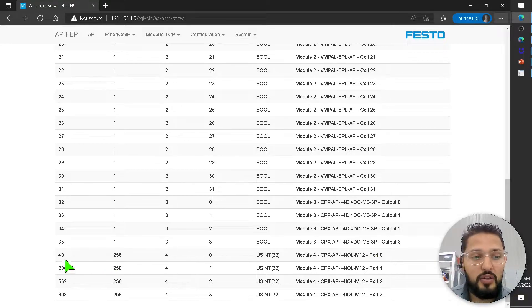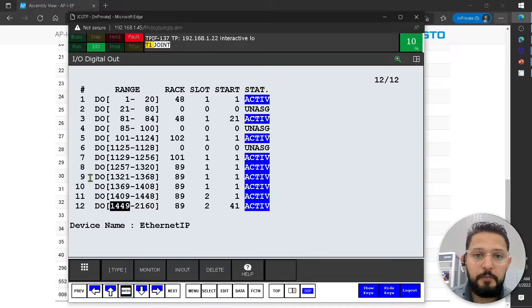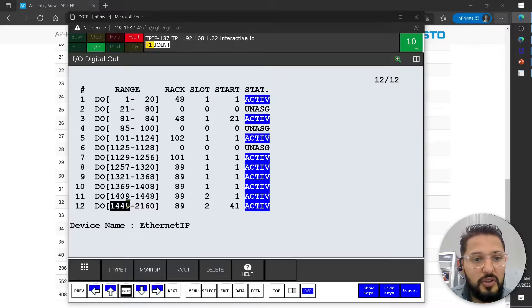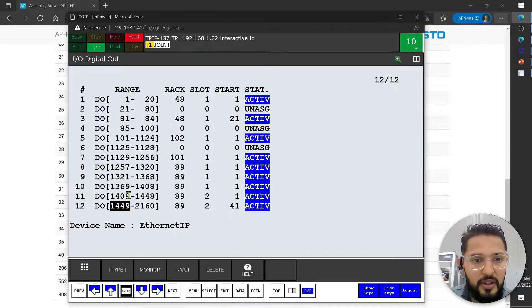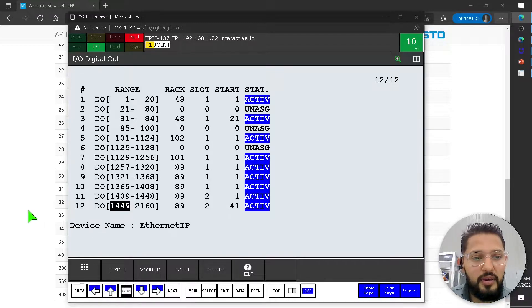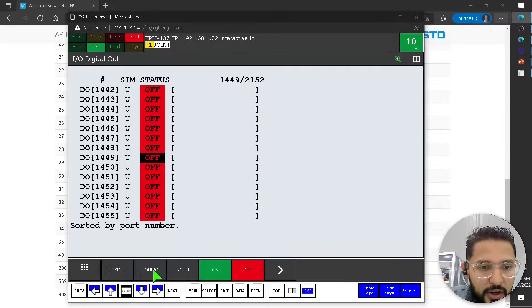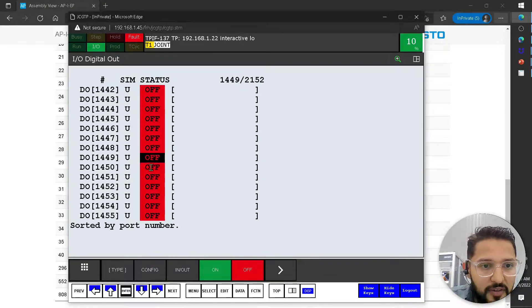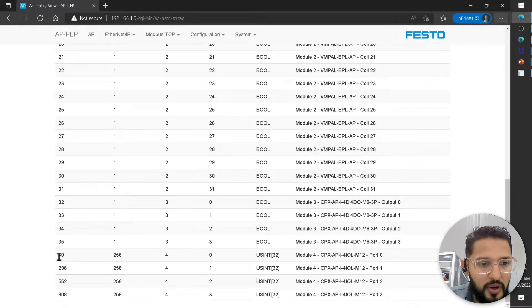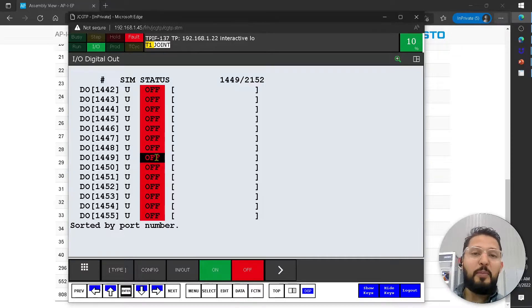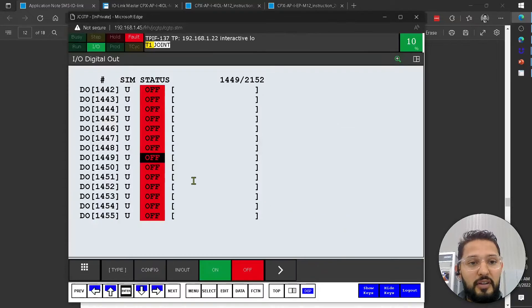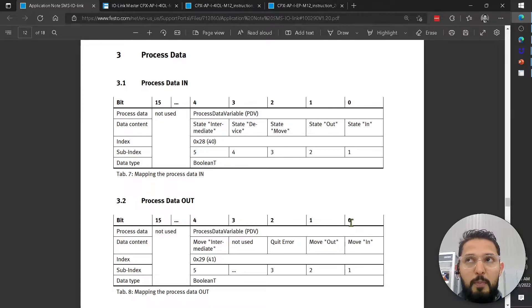the 40th bit is where I start with my IO-Link device. And this is port zero where I'm connected right now. So bit 40, right? So right here is my 40th bit. This goes from 1409 to 1448. This is my 40th bit. So now I'm going to say monitor, and this is the first byte. I know for a fact that the bytes are swapped. So this process data is not going to start from here. This process data is actually going to start from bit 8.